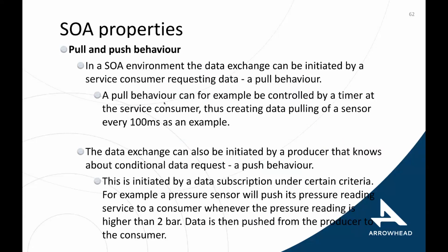Other SOA properties is that here we can now implement easily both the pull, exactly as the same as the SCADA DCS systems, and a push behavior, meaning type of a subscription to data if something happens. So if, for example, a pressure sensor is reading the data, when the pressure is changing to higher than, in this example, 2 bar, then data is pushed from that producer to the consumer.